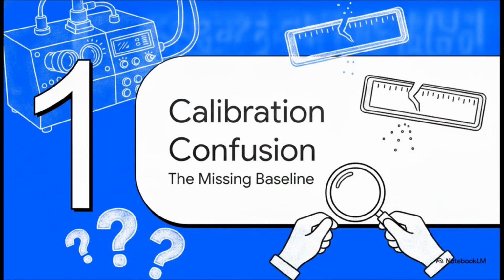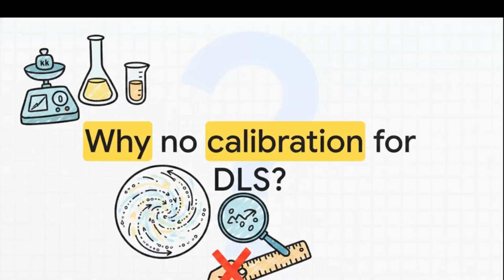Section 1. The calibration confusion. Picture this. You've just unboxed this gorgeous, highly sensitive DLS instrument. Your absolute first instinct, because it's been drilled into us since day one of science class, is to calibrate the thing, right? You look for the baseline settings, you check for the reference materials, and there's nothing. Zero. Which brings us to the exact question clients frequently ask the experts over at Brookhaven Instruments when they're trying to validate their tools. Why on earth is there no calibration for dynamic light scattering?